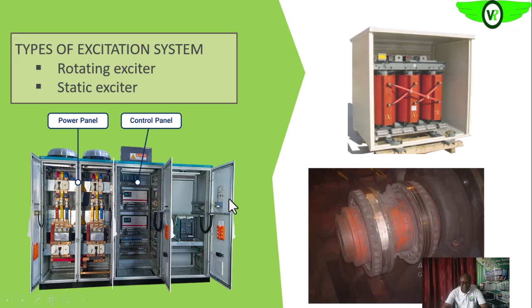So now if you look, this is the excitation transformer. The excitation transformer is connected to the output of the main generator, as we'll see later. It will step the voltage down to the excitation voltage. Assuming our main generator is delivering, say, 11 kV as an example, this transformer will take it down from 11 kV to maybe 415. That 415 will be fed into this static excitation unit, which will convert it to DC that will be fed to the main field of the generator to magnetize the main field. So that is what we are seeing here now.